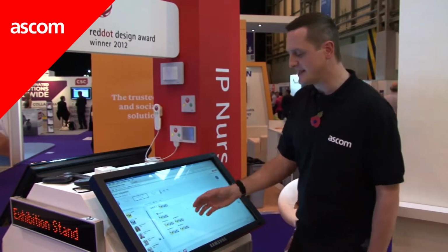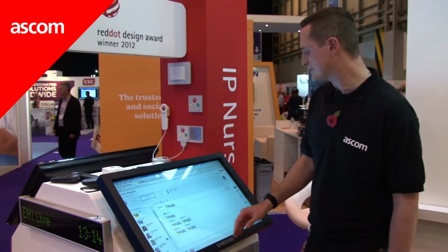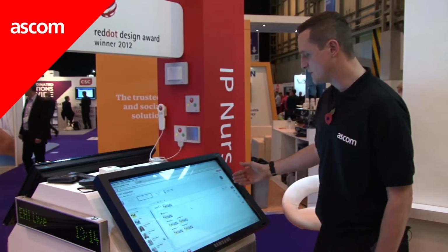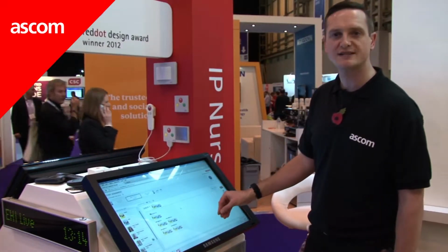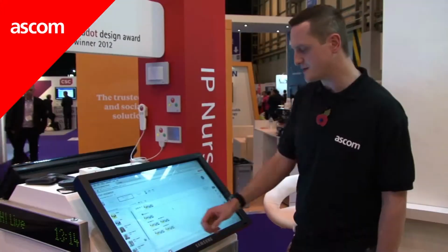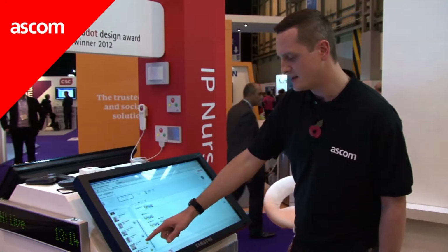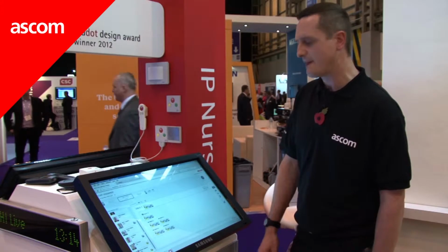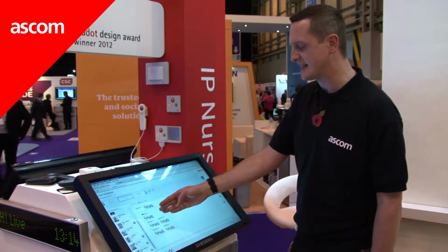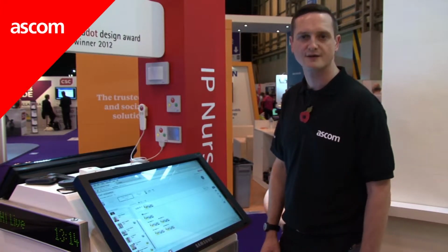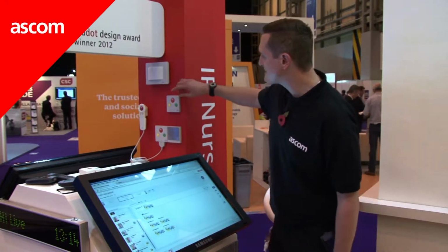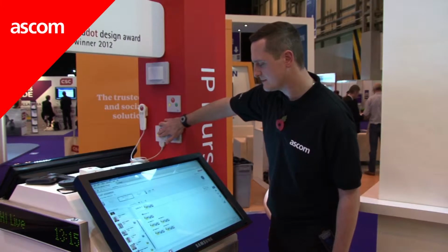Now, staff assignment is where you can assign the nurses and the doctors or groups of nurses to particular alarms or particular beds and patients within your ward. So here we have our nurse call setup. So I've got a yellow team as the first responders, which will actually incorporate a few nurses on shift. And if they don't respond, it will escalate to the next team of nurses and then finally to an individual if required.